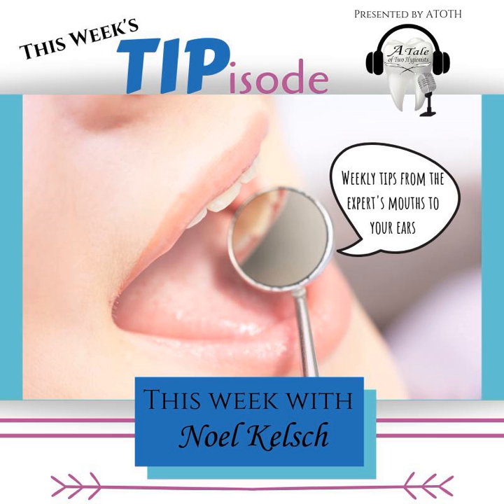And I know we've had some speakers out there saying that you could use something like Spic and Span. Not recommended because these could impact your instruments over time. Follow the recommendations by the instrument manufacturer as well as the recommendations for ultrasonic use when choosing that additive.